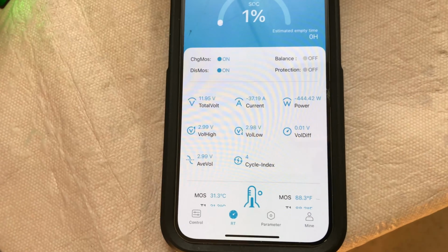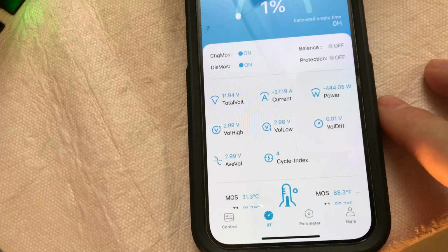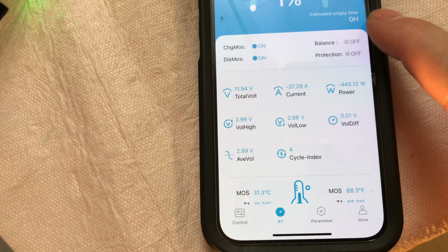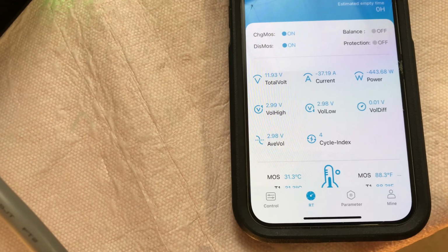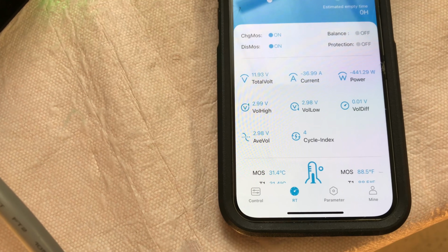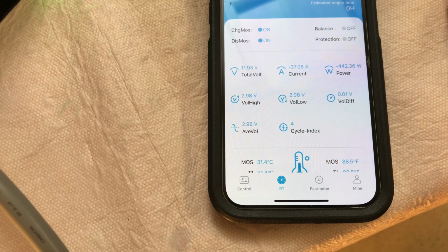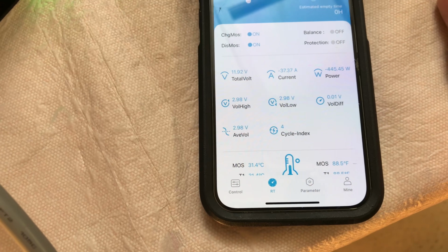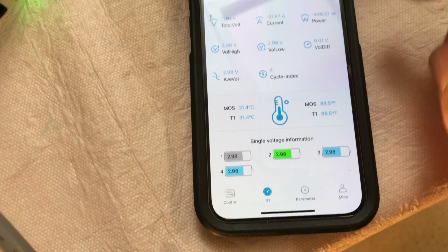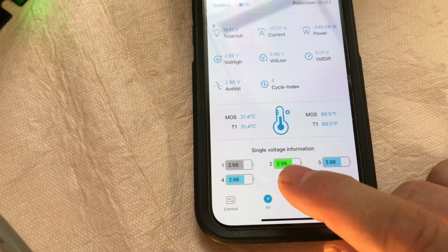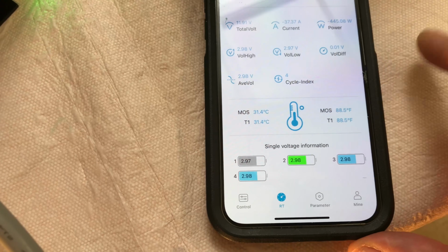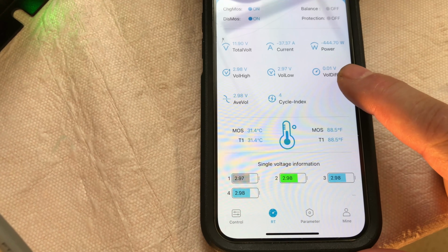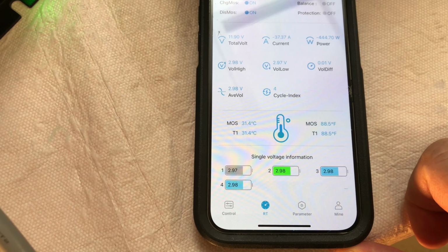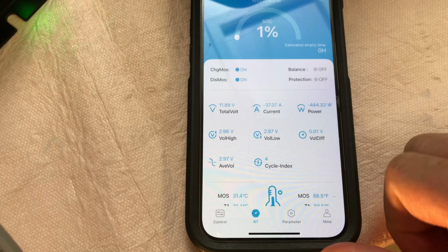Well, we're down to 1% on the discharge. It says no time remaining. 11.93 volts, still pulling 36 amps of current at 442 watts. And clear at the bottom, we are almost perfectly balanced.